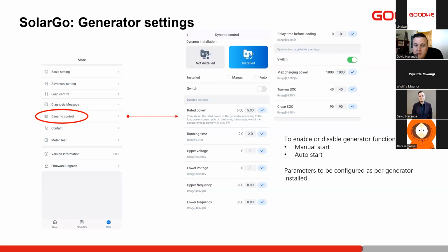The delay before loading, so the delay before the inverter connects to the generator. So you might want your generator to auto start. You want it to warm up a bit first before we put the load on and start using the generator. So yeah, you can select maybe 60 seconds or more, and then it will wait a bit longer once the generator is started before it connects to the generator.